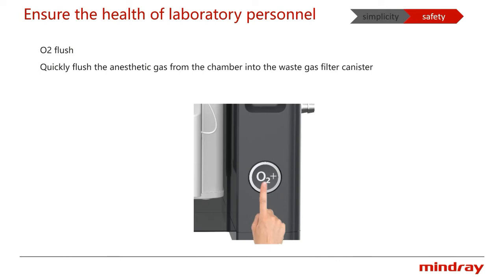Here we can find an oxygen flush button on the body of the machine. This is for quickly removing all the waste gas from the induction chamber into the waste gas canister. Leakage would be significantly lower when getting the rodents from the chamber after flush. So when you open the induction chamber, less anesthesia gas will leak into the air in the lab.